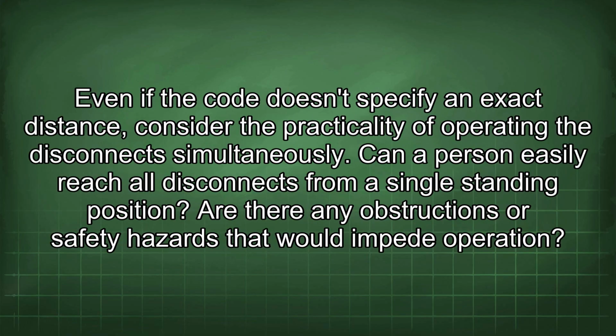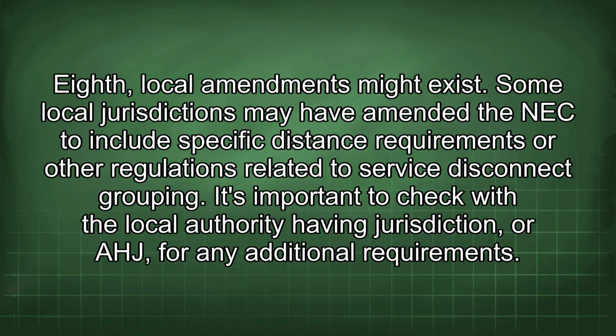Even if the code doesn't specify an exact distance, consider the practicality of operating the disconnect simultaneously. Can a person easily reach all disconnects from a single standing position? Are there any obstructions or safety hazards that would impede operation? Eighth, local amendments might exist. Some local jurisdictions may have amended the NEC to include specific distance requirements or other regulations related to service disconnect grouping. It's important to check with the local authority having jurisdiction, or AHJ, for any additional requirements.